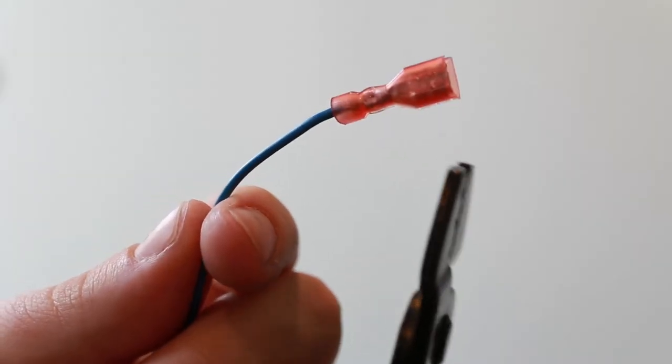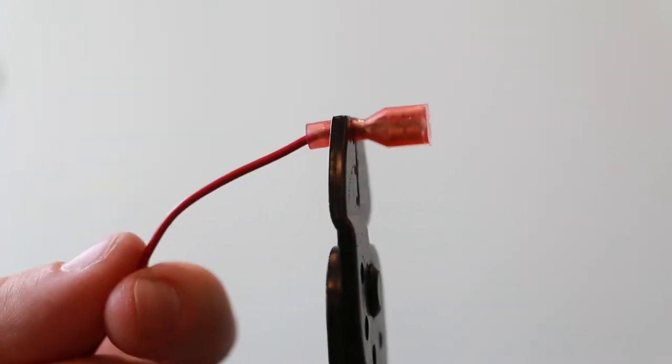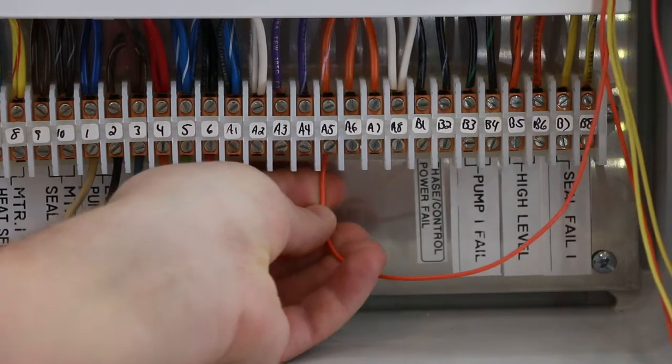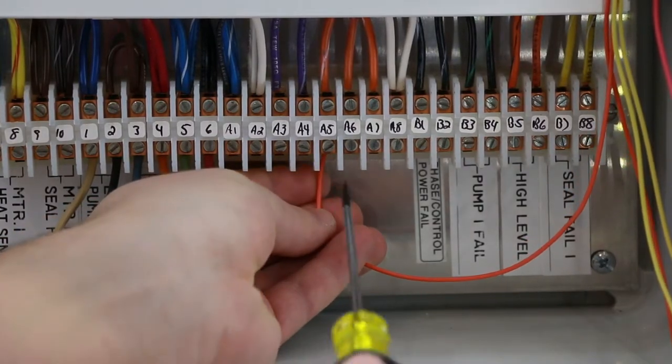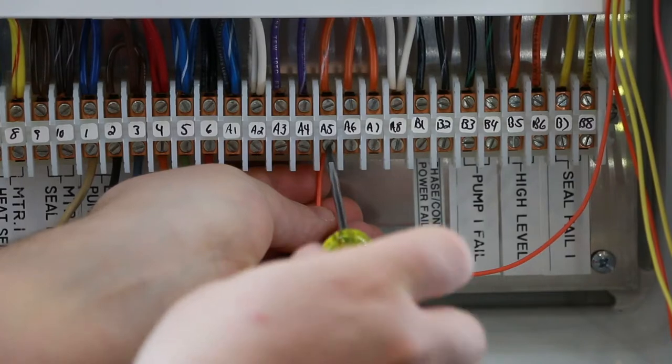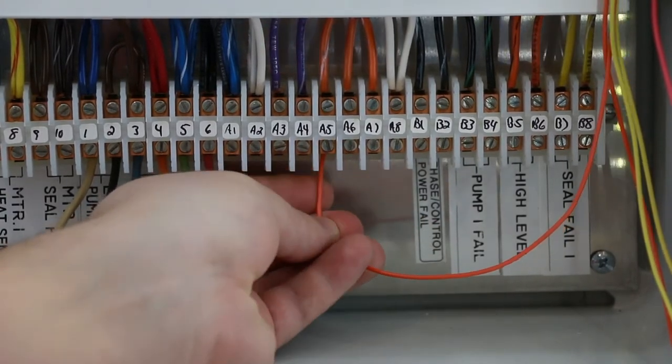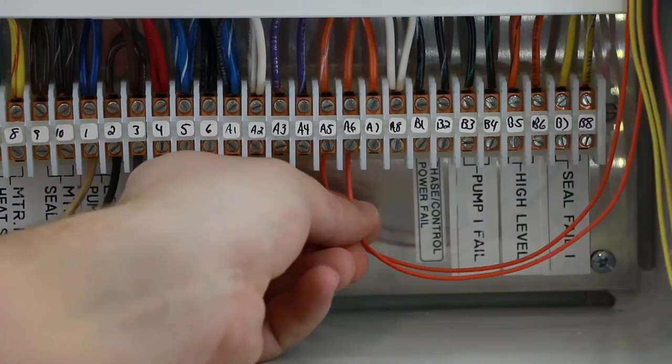Crimp the quick connect terminals onto the end of the battery leads. Land the two orange alarm wires on dry contacts within your panel. Be cautious not to apply any voltage to the orange contacts as this will damage the OmniBeacon. Make sure to verify that your connections are snug.